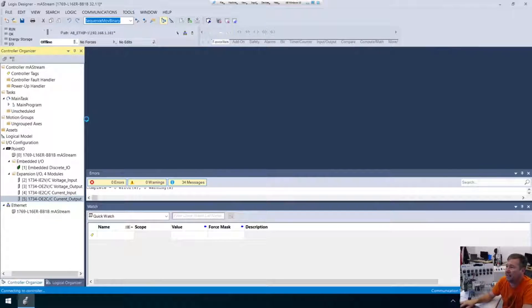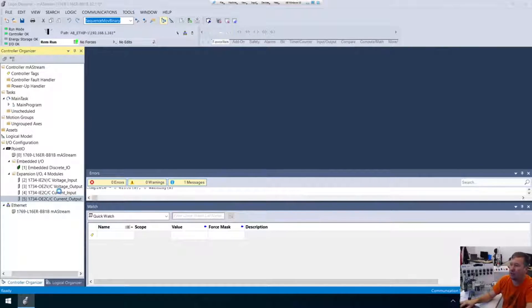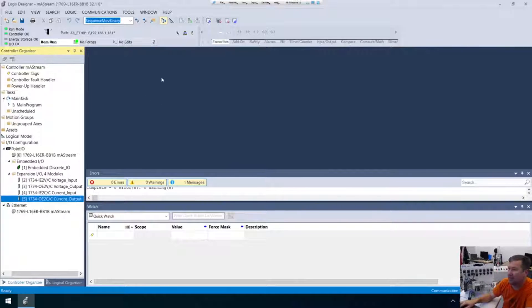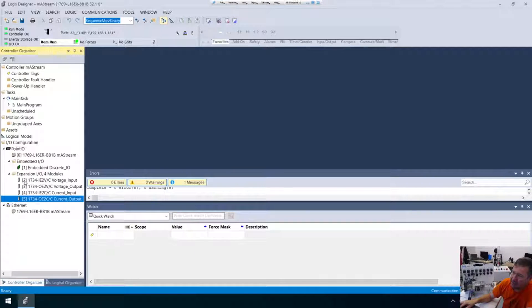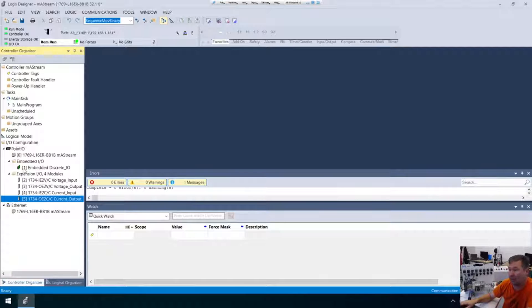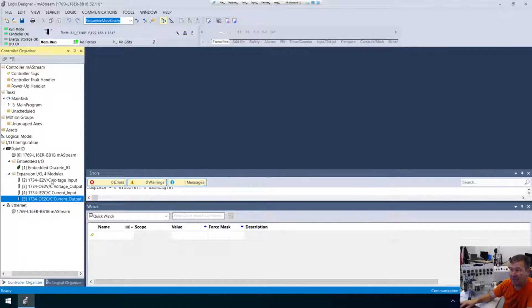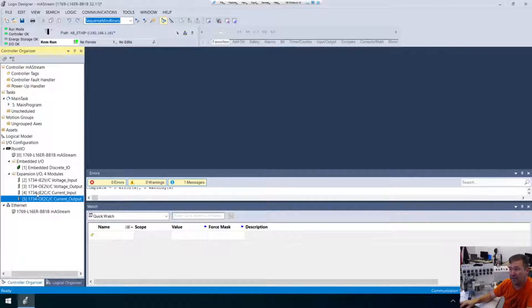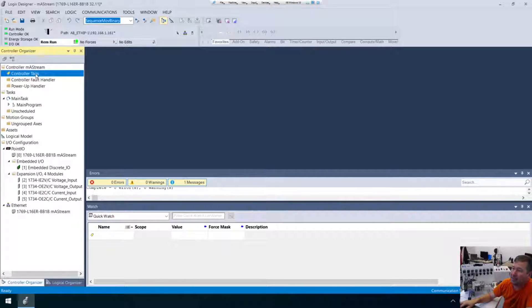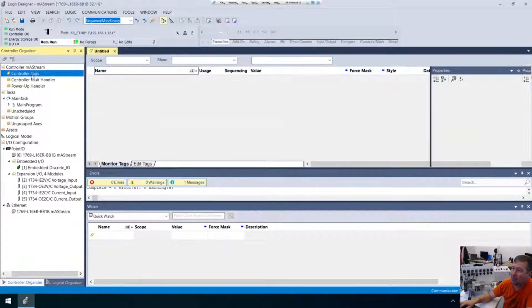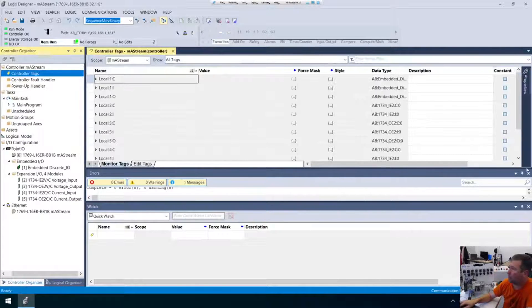Okay, now the next thing we're going to do is figure out where is this analog input. So I added them in these expansion modules here. And if you notice it, there is a number in front of this expansion. So our embedded is 1. And that means that's local colon 1. So our first module is going to be 2. Our second module is going to be 3. And our third module is going to be 4. So we need to go to local 4.